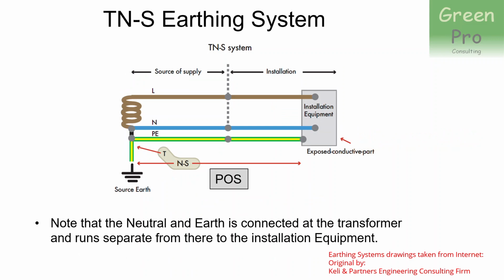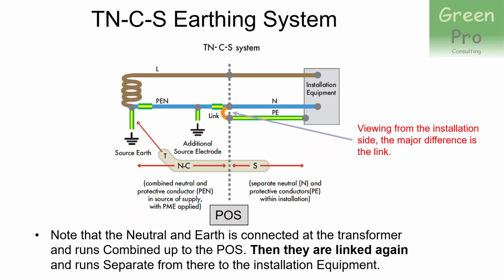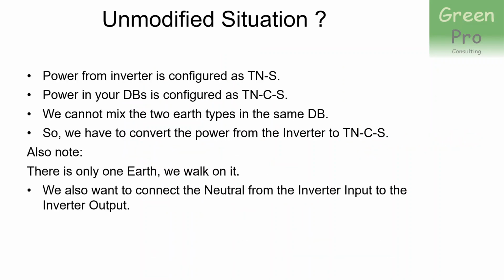I'll just go back. You can see there's no link with a TNS system, and with a TNCS system, there's a link between neutral and protective earth at the point of supply. So that is obviously what we have to duplicate.